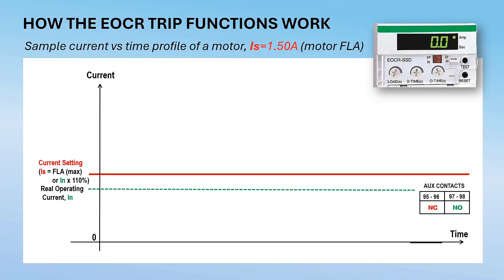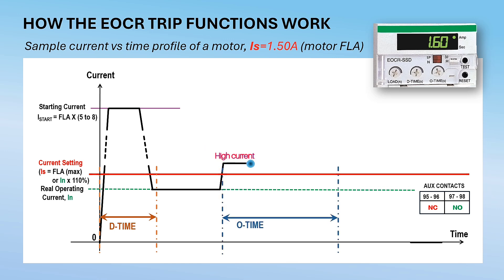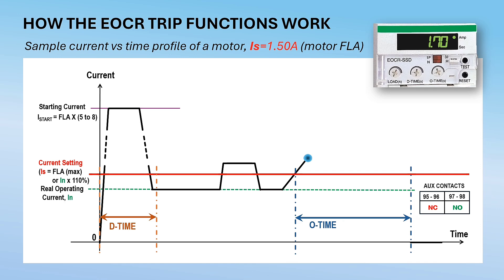How the EOCR trip functions work: on every start, the D-time also starts counting. The relay senses five to eight times the motor rated full load current. The EOCR will not trip if the starting current goes below 200 percent before the D-time elapses. After the starting period, the motor goes to normal current level. When the current suddenly goes above the load current setting, the O-time starts counting. If the overload is not maintained until the O-time elapses, the EOCR will not trip and the O-time resets to zero. When the motor current goes above the load setting again, the O-time starts counting again. If the overcurrent is maintained up to the end of the O-time setting, the EOCR will trip, auxiliary contacts change from NO to close and NC to open, and a reset is required to normalize the relay.